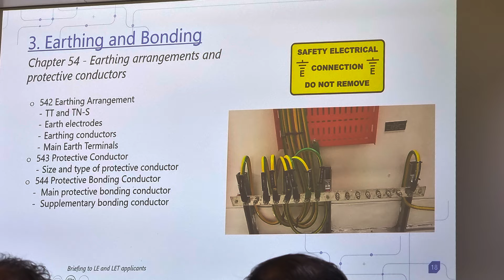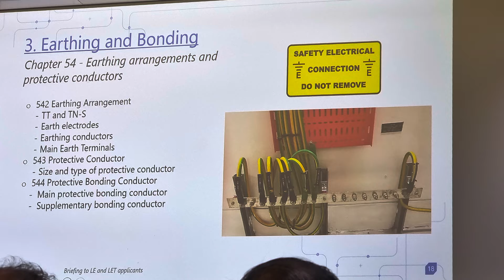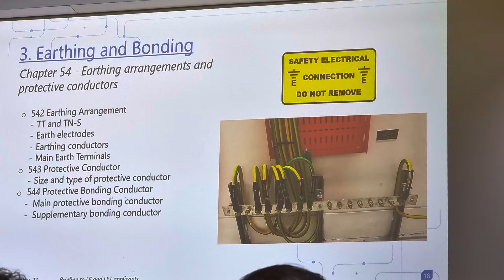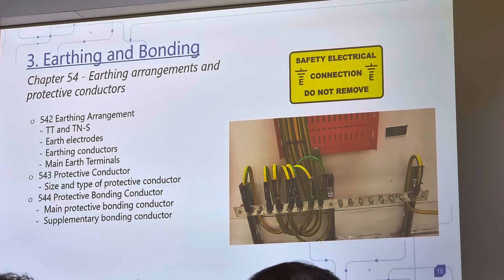Bonding conductors, what is a bonding conductor? So talk about the installation. What is the bonding conductor? Which is considered as the bonding conductor? You cannot use the bonding conductor all the way. So which is not? How is it bonded to the MET? MET stands for main earth terminal. This is the terminal that you find in every installation. This is the main one. All the conductors are bonded to the earth through this MET.